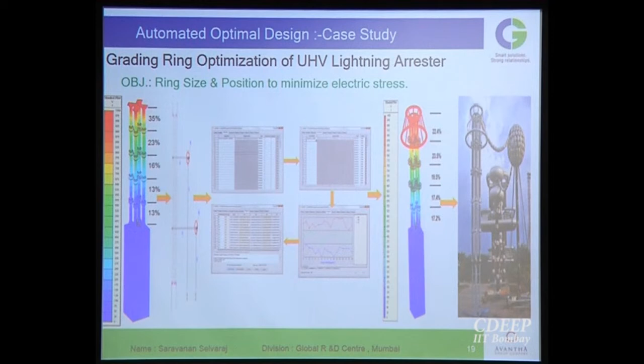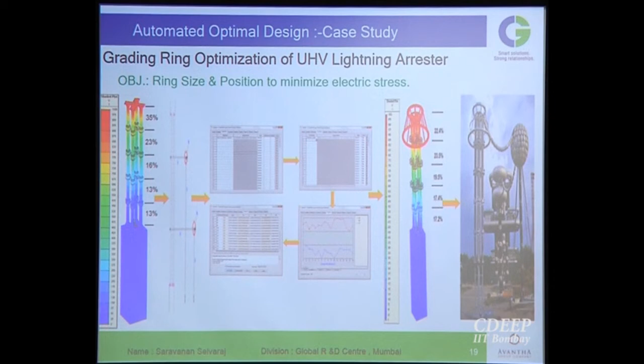So we used the optimizer with the given state variables, constraint and design variables, which runs the optimization procedure and throws out very different designs. It gives a number of designs, and from that the optimum or feasible design is selected based on the manufacturing feasibility studies. So the similar grading ring is designed for a UHV lightning arrestor. You can see a near uniform voltage distribution is achieved, and the same thing is tested actually.